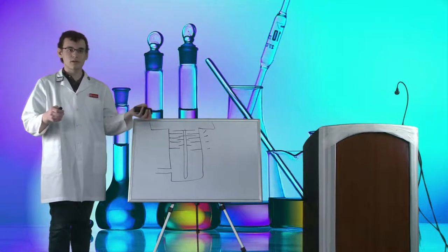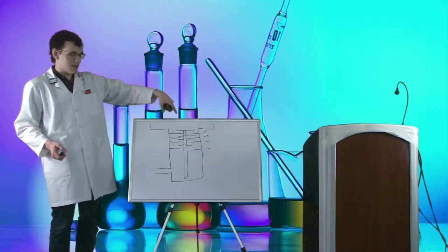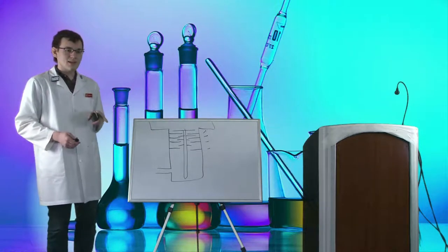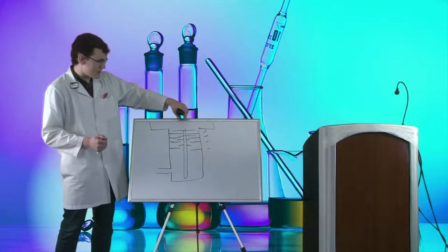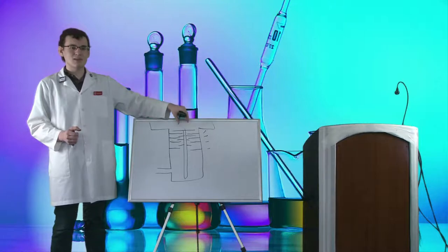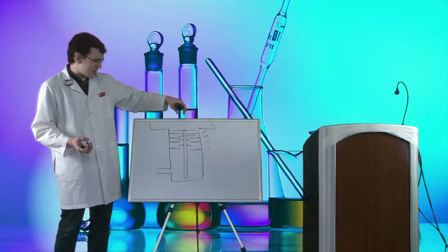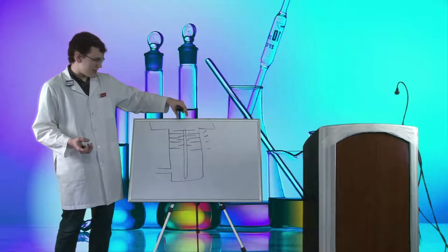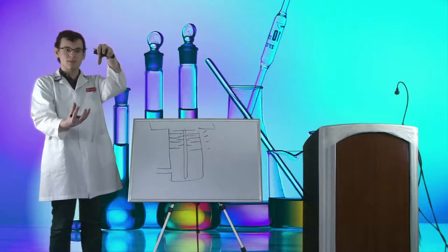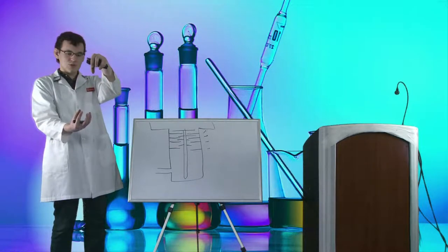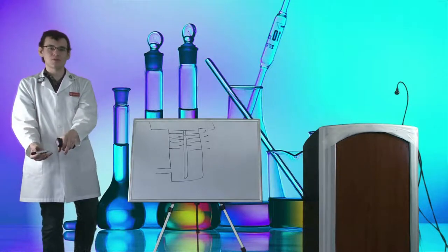These pumps require really amazing bearings to run something at 10,000 RPM. Often there is active magnetic levitation — magnetic coils sit on top of the pump and the controller uses the magnets to balance the rotor so it's not even touching anything because it's spinning so fast. These pumps are very expensive because they're good, and if mistreated they have the tendency to catastrophically destroy themselves in spectacular fashion.